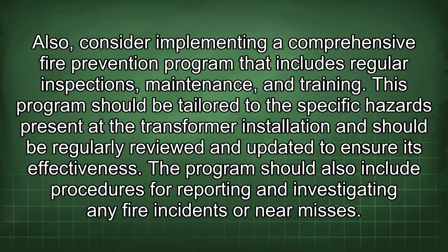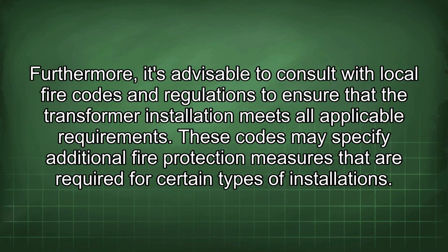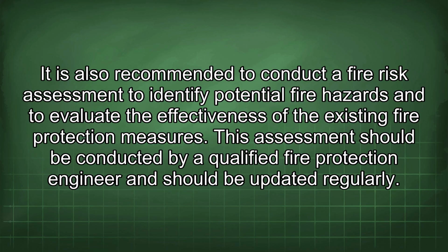The program should also include procedures for reporting and investigating any fire incidents or near misses. Furthermore, it's advisable to consult with local fire codes and regulations to ensure that the transformer installation meets all applicable requirements. These codes may specify additional fire protection measures that are required for certain types of installations. It is also recommended to conduct a fire risk assessment to identify potential fire hazards and to evaluate the effectiveness of the existing fire protection measures.